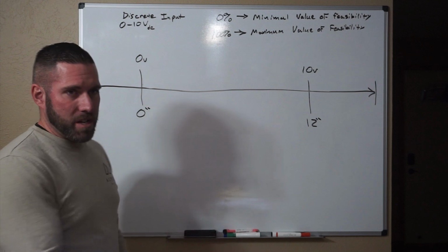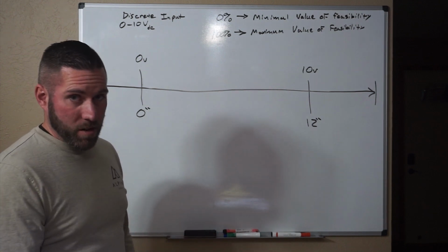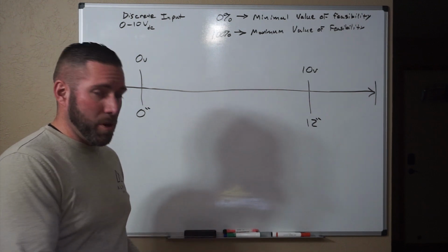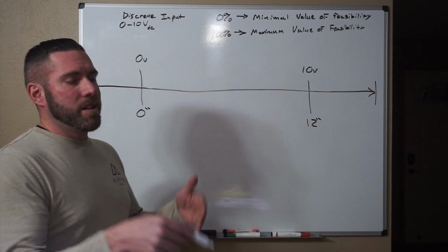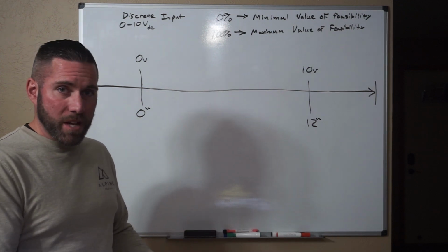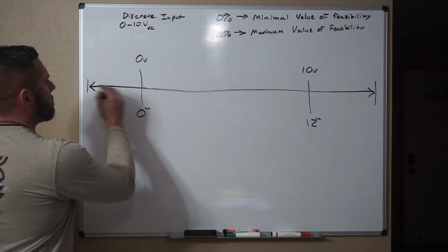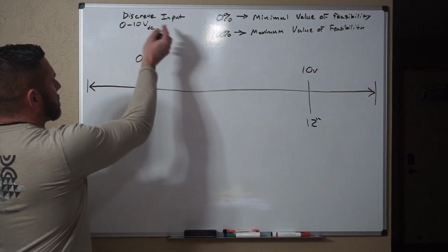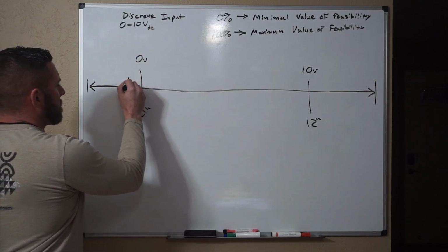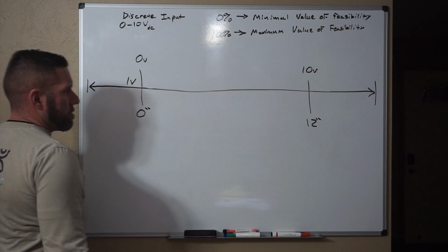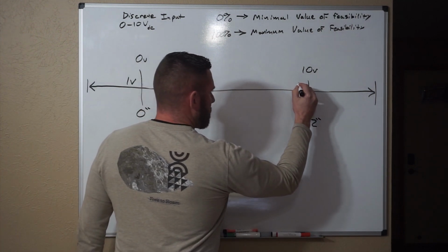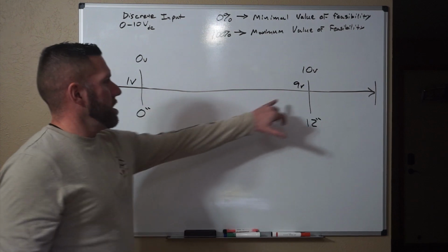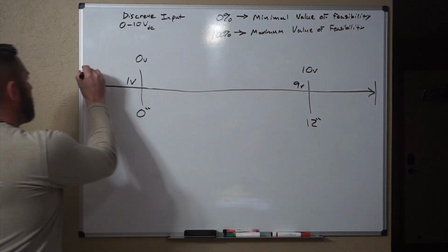So the module is much more capable of reading an input and it can compensate. You cannot compensate on a sensor. It puts out what it puts out. That's what the chip or the small SMD circuit driver in it is actually programmed or set up to do statically. So you would set, we're doing a 0 to 10, so we'll call this 1 volt to 9 volts.